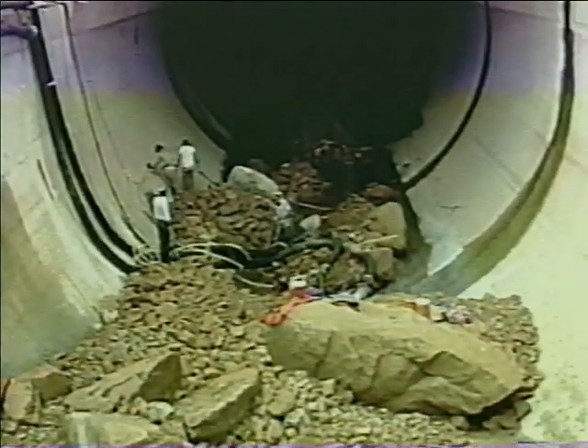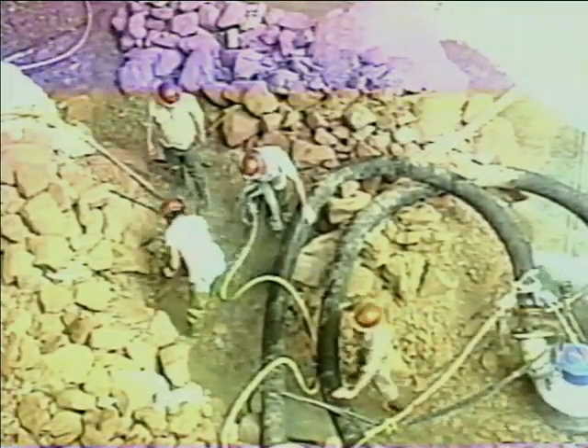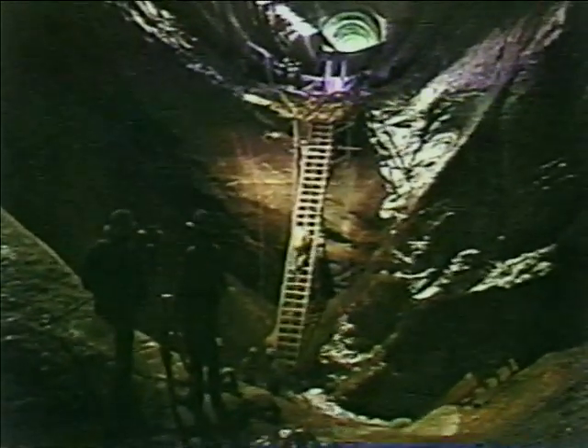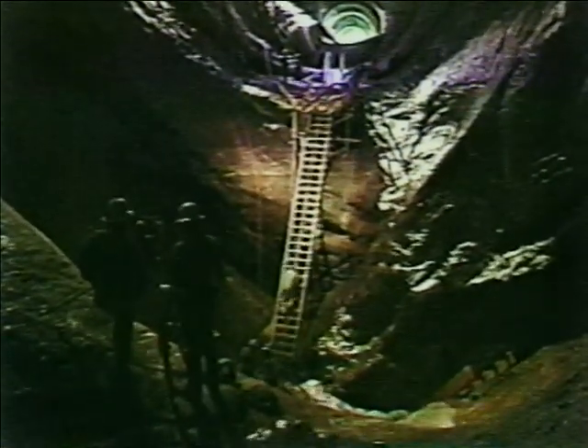It was found that cavitation had dug deep holes 8 to 10 feet deep and 25 feet wide. When the water was pumped out, the spillway disclosed an amazing array of rock rubble that had been gouged from the tunnel floor, including this huge boulder that had been lifted out by tons of falling water. Most astonishing of all was the big hole at the elbow section, found to be 32 feet deep, 40 feet wide, and 150 feet long. It took 2,500 cubic yards of concrete to fill the hole.